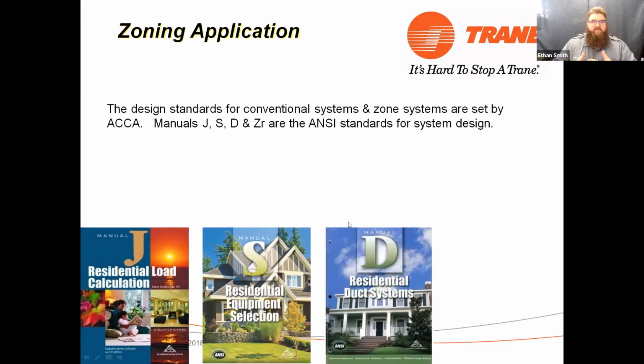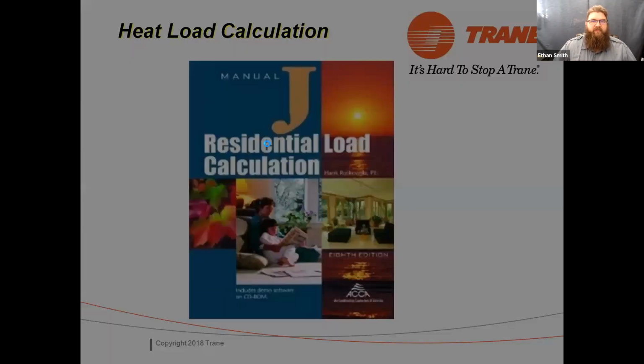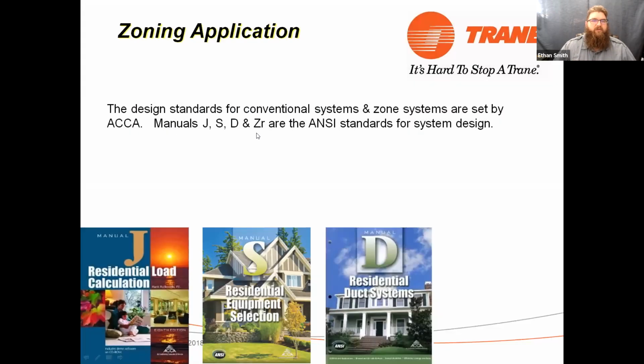So a zoning system takes all of the stuff that we're used to talking about, professing that we adhere to. We've got Manual J for load calculations, Manual S for equipment selection, and Manual D for duct systems. If you've never read those manuals or you don't know what they are, I highly encourage you to investigate them in depth. They make great nightstand reading. If you're ever having a bout of insomnia, go ahead and open up Manual D for about 20 minutes. You'll be out like a light. We have to wrap all of this stuff together in order to make a zoning system operate properly. In fact, in addition to Manual J, we'll talk about Manual ZR, which was released a number of years ago. But let's start with Manual J.